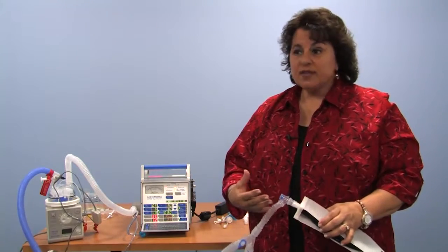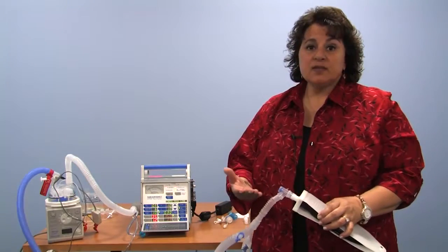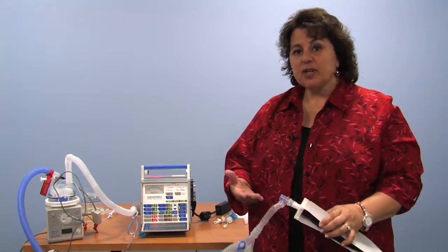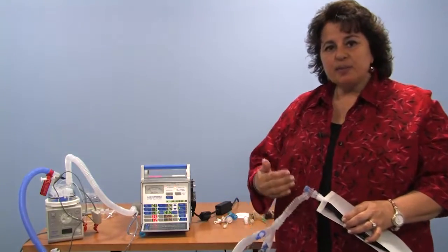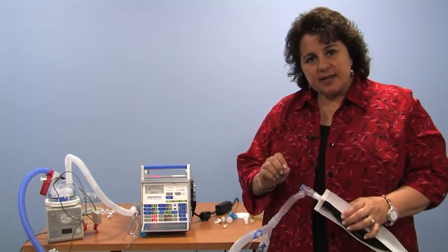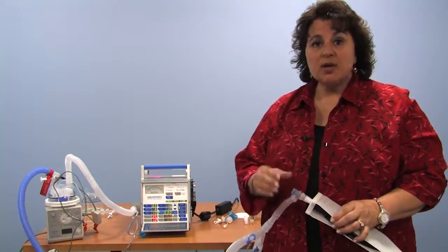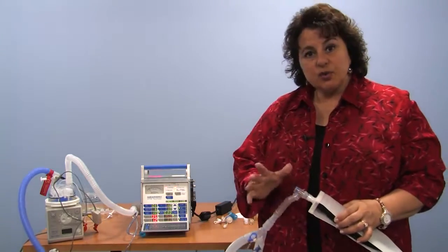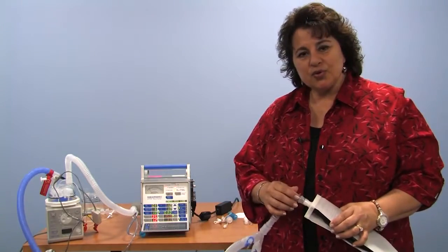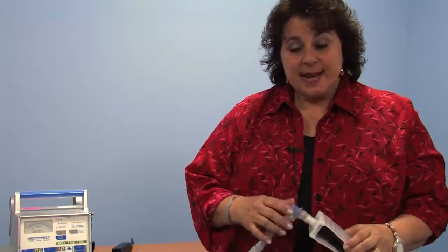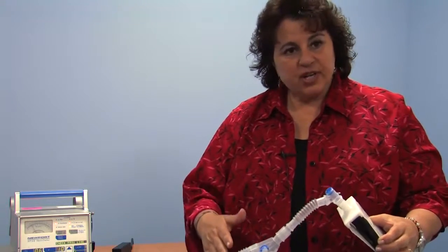If you're at the doctor's office or going to the hospital, perhaps by ambulance, or perhaps you have an appointment during the day and your child's on nighttime support and you don't have the ventilator with you, it's important to know what it's set on. So either jot it down somewhere, or if you have a smartphone with a camera, take a picture of the machine while it's on your child so that you can show the providers at the local facility that you go to what the settings are for your child. As far as cleaning the equipment and changing the ventilator circuitry, the ventilator should use sterile water in the humidifier if you're using humidification, and refer to your durable medical equipment company for how often to change the circuitry. Typically it's twice a month or every other week.